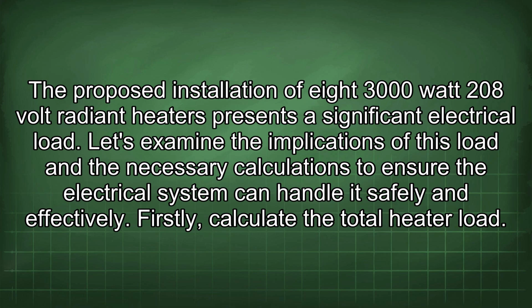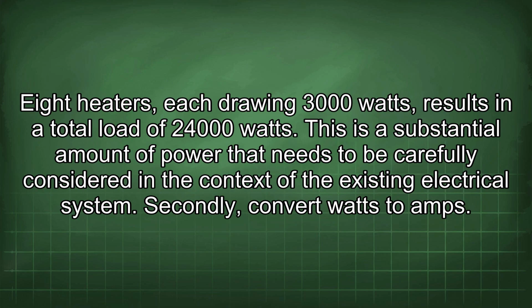Let's examine the implications of this load and the necessary calculations to ensure the electrical system can handle it safely and effectively. Firstly, calculate the total heater load. 8 heaters, each drawing 3000 watts, results in a total load of 24,000 watts. This is a substantial amount of power that needs to be carefully considered in the context of the existing electrical system. Secondly, convert watts to amps.